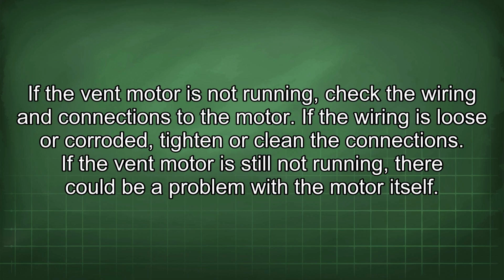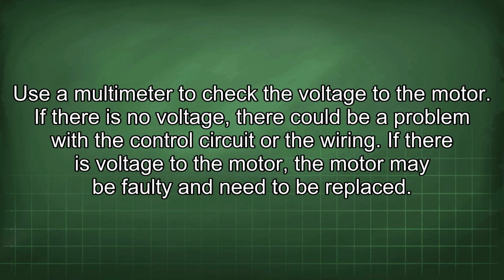If the vent motor is not running, check the wiring and connections to the motor. If the wiring is loose or corroded, tighten or clean the connections. If the vent motor is still not running, there could be a problem with the motor itself. Use a multimeter to check the voltage to the motor. If there is no voltage, there could be a problem with the control circuit or the wiring. If there is voltage, the motor may be faulty and need to be replaced.